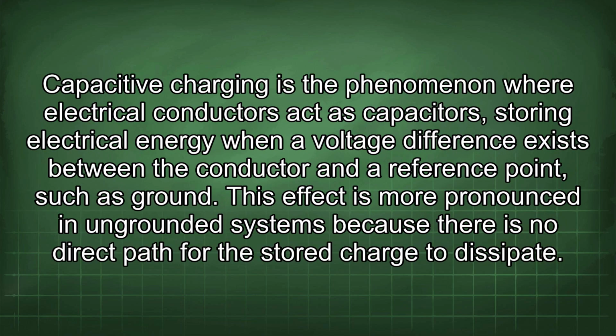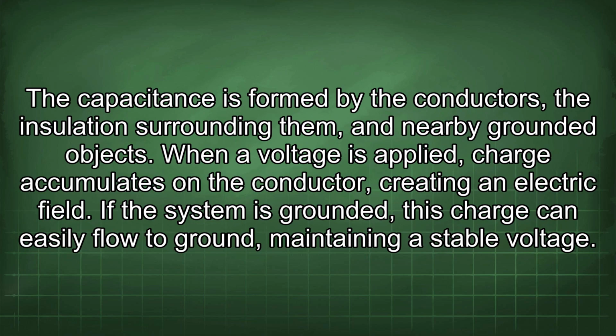Capacitive charging is the phenomenon where electrical conductors act as capacitors, storing electrical energy when a voltage difference exists between the conductor and a reference point, such as ground. This effect is more pronounced in ungrounded systems because there is no direct path for the stored charge to dissipate. The capacitance is formed by the conductors, the insulation surrounding them, and nearby grounded objects. When a voltage is applied, charge accumulates on the conductor, creating an electric field.